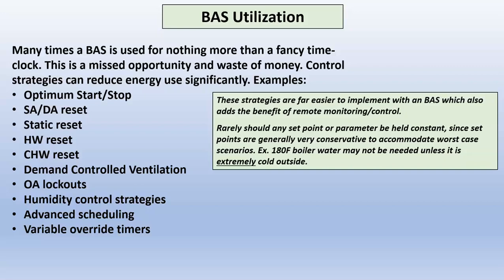That's an opportunity. Optimum Start actually looks at the room temperature, has an algorithm that studies the rate that it changes to heat or cool that room. The really good ones actually also look at the outdoor air temp, and they can calculate about how much time it's going to take for the system to ramp up and get you to that temperature that you want.